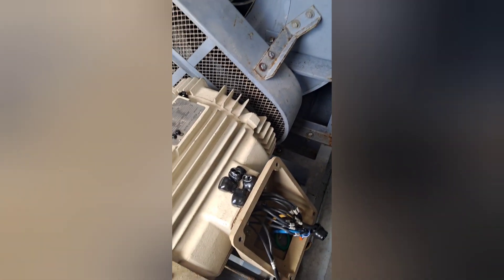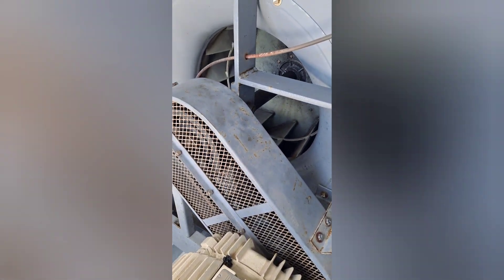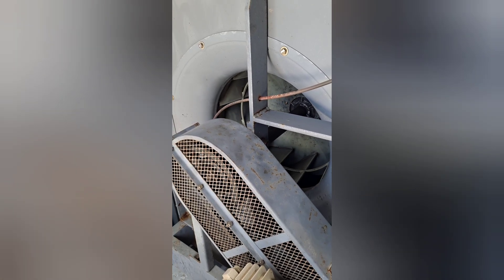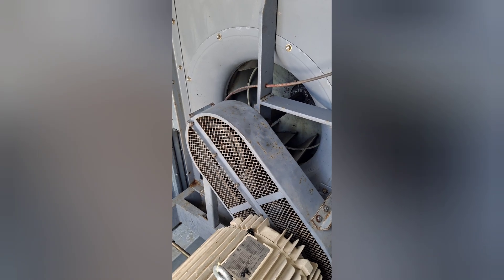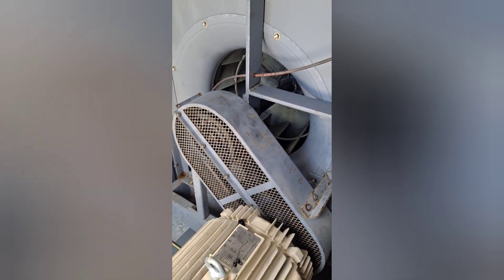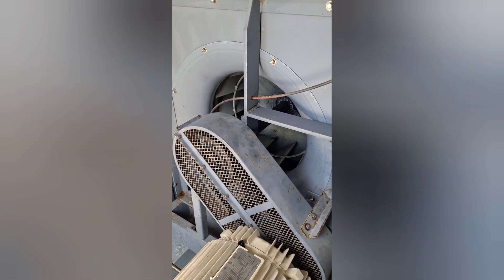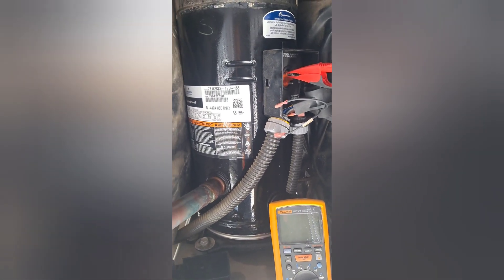I'm doing another one of these motors, putting Polaris connectors on, and I happened to notice something — the unit is off, right — but look what's happening. If you pay attention to that, it could tell you that you have a building pressure problem, which the building engineer did confirm when I asked him about it. So now I'm testing this compressor.